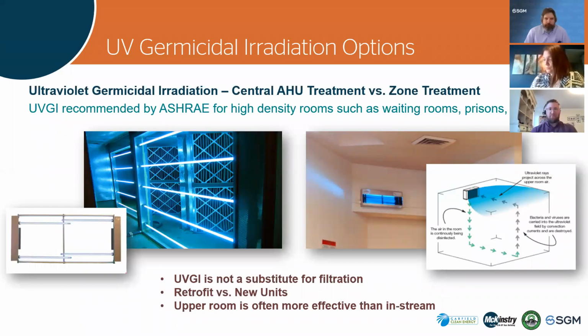Yeah, so I'll jump into UV here quickly. So UV, like I said, is recognized by ASHRAE as an effective technology, but its effectiveness really depends on exposure time. So this is something that's very difficult to retrofit into an existing air handler. You can do in-duct or in-unit UV, or you can do in-room. So in a retrofit application, it's likely that in-room is going to be the more effective solution. The air is just moving too quick in most air handling units to retrofit.